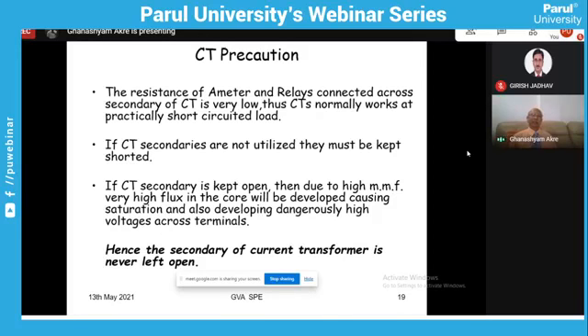Now, CT, after you make the secondary, primary and all this, requires particular precautions also. You know that CTs are connected across the meter or relay. If suppose the meter gets open circuited, what will happen? Everybody knows and has heard that very high voltages will develop across the secondary. If I take the example of 100 by 1, primary is 100 amperes and the secondary is 1 ampere. So long as the secondary is shorted through the load, it will carry only 1 ampere, and the voltage developed across it is according to the VA burden, or in proportion to the load. But if it is open circuited, what happens?